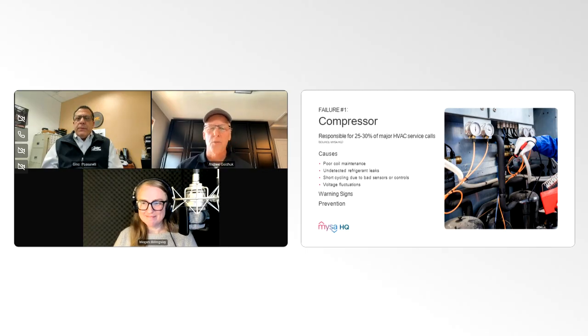Some of the more obvious things, I believe, too, whether they will actually hear it or not, because all this equipment is on the roof, but you can hear grinding noise or constant clicking, very loud, abnormal mechanical sounds, hard starts. So it can be very obvious if it's loud enough or if it can be heard into the building. A technician, obviously on site looking at the equipment, is going to hear that right away and know that there's going to be a problem. Depending on the type of failure, whether it's related to refrigerant charge, there could be ice forming on the refrigeration lines.